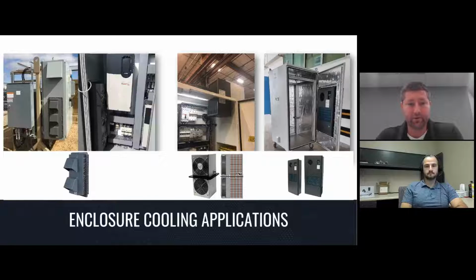On the left is an outdoor drives cabinet using our HSC 68, which has three different heatsink fan combinations, with a rain guard overlaid on the fans for outdoor use. The customer came to us, specified their heat load and environmental conditions, and we quickly directed them to a product that would work.